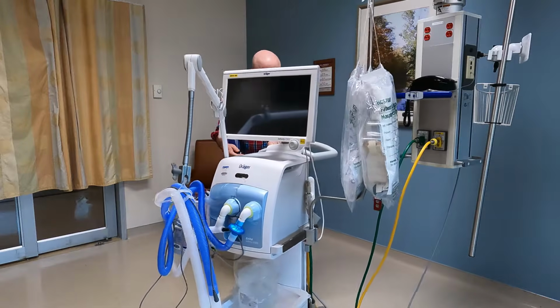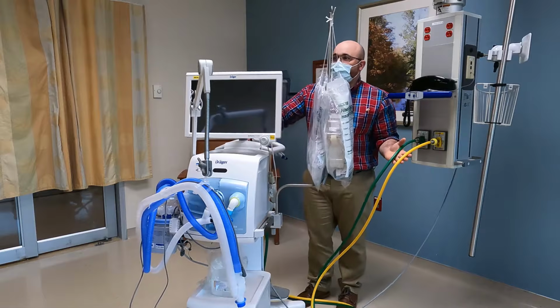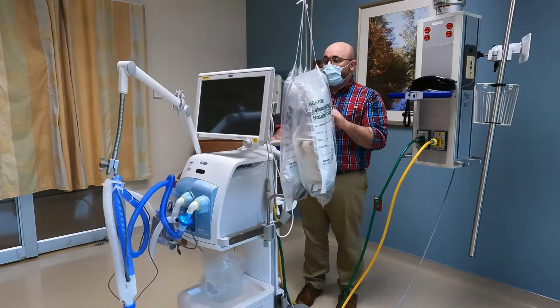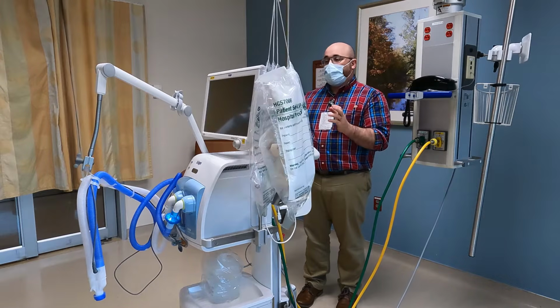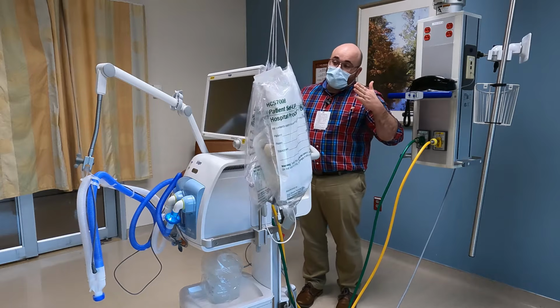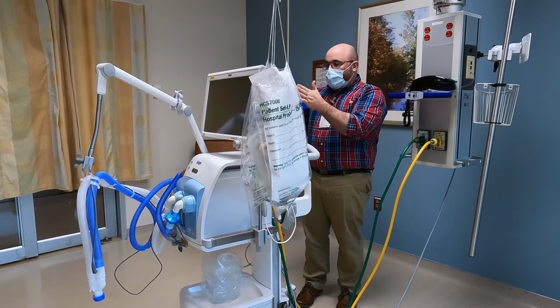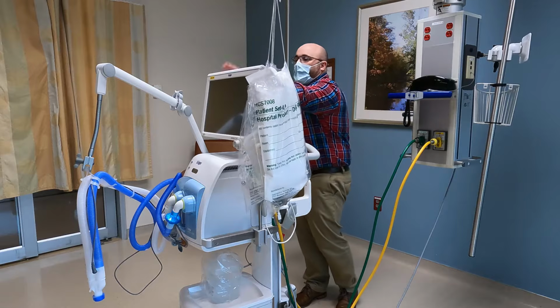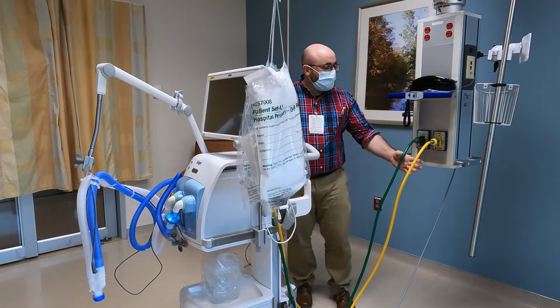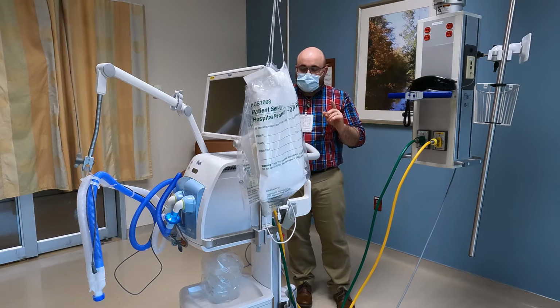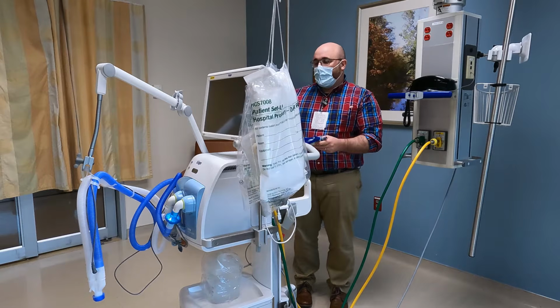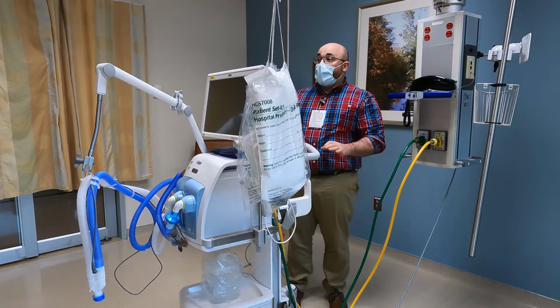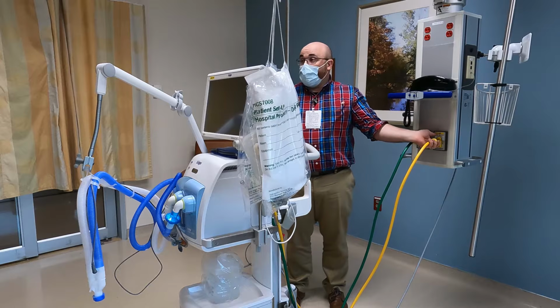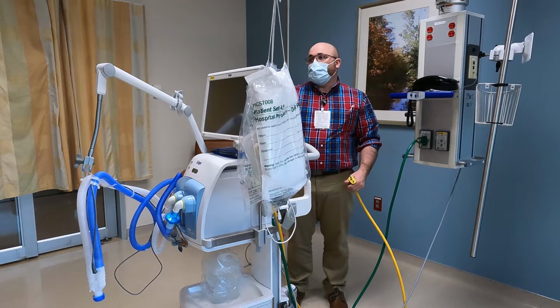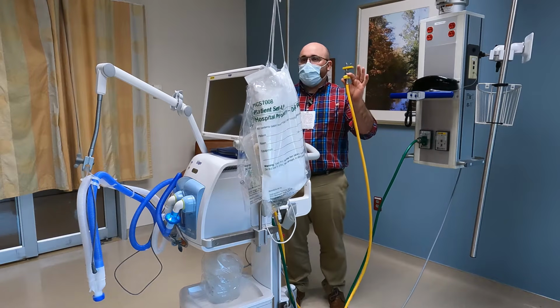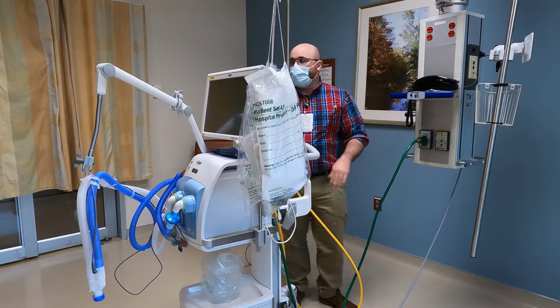One other important aspect is it has to be plugged into air and oxygen at all times. Inside of this is a blender, so it has what's called a proportioner valve. So the pressure will come in from air and oxygen. It will proportion it appropriately to give you the FiO2 that you have set. So you always have to have those plugged in. If for some reason we had some kind of natural disaster and we lost air, we could pull air off, put it on 100% oxygen, it would work and not beep.